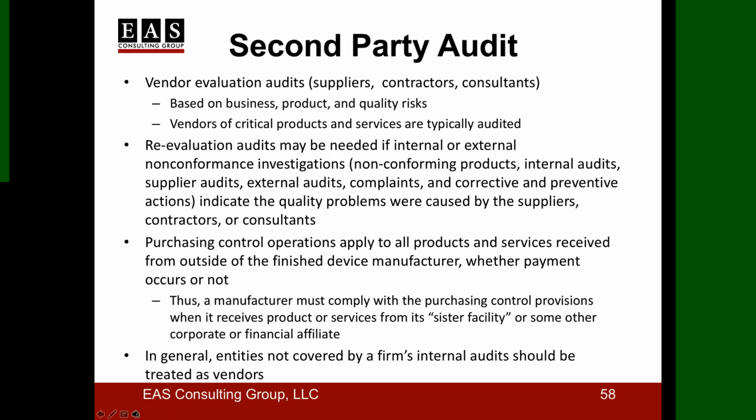So if that product is indeed a finished medical device product, then not only do they have to conform with your requirements, they have to conform with FDA and EU and Health Canada and Brazil and whatever other requirements you place upon them too. And so they are inspected and audited by FDA, notified body, Health Canada, etc., just like you are.